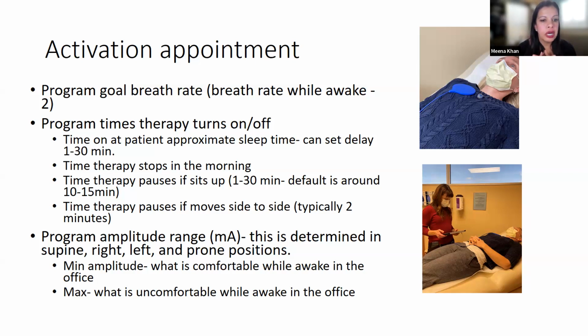And then we program the amplitude range in milliamps. Again, this is the minimum and the maximum. And we do it in all 4 quadrants: supine, right, left, and prone, because they may tolerate different amplitudes in different sleeping positions, and also their breathing might be different in different sleeping positions. So the minimum amplitude that's programmed is what's comfortable for the patient to tolerate while they're awake. And the max is a little bit below what's uncomfortable. And then that's the range. And when they turn the device on, the device is reading their breathing. If they're not at that goal rate, it will increase that milliamplitude within that range until it captures the goal rate.